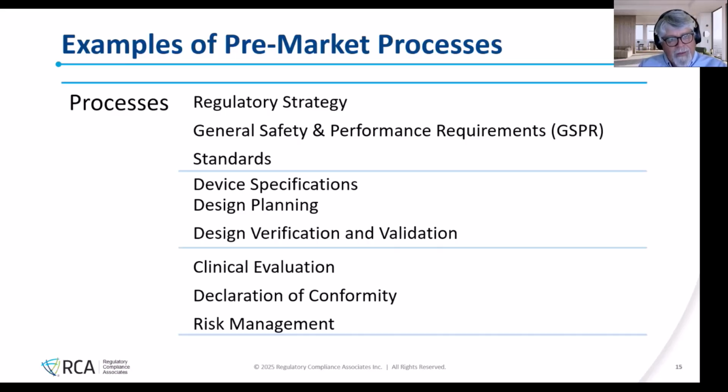Standards are important. And then part of the conceptual stuff is that you have to come up with device specifications. Device specifications is, from a perspective, what's its intended purpose, what's its intended use, indications for use, what's its biocompatibilities, is there clinical stuff? All that has to be addressed as an input going into design planning. And then you have design verification and validation. The reality is design control is a bridge, if you will. It's a connector bridge between pre-market requirements and production requirements or production.